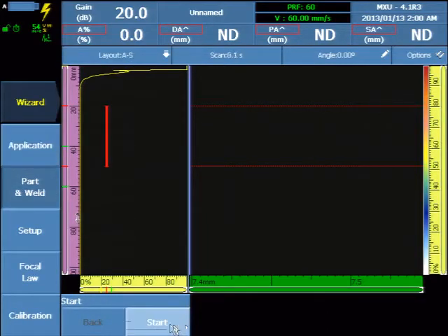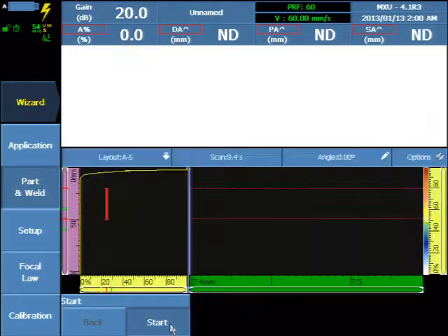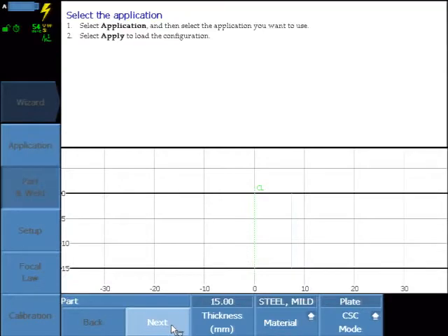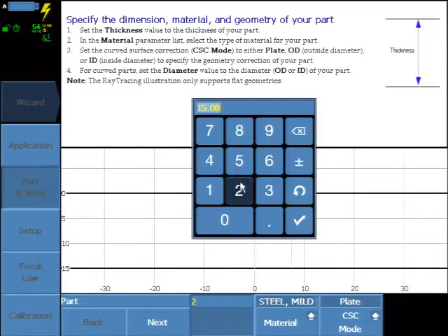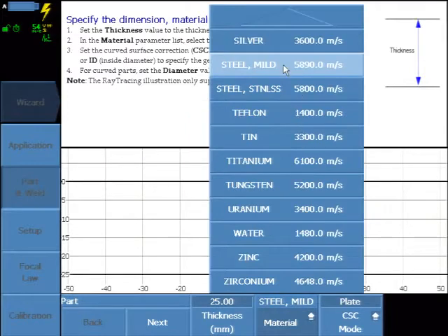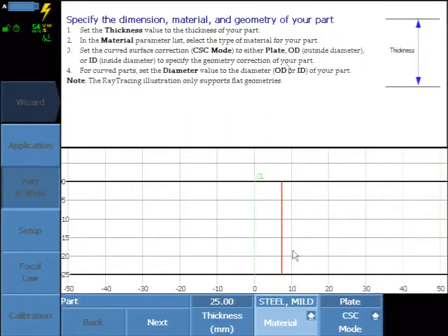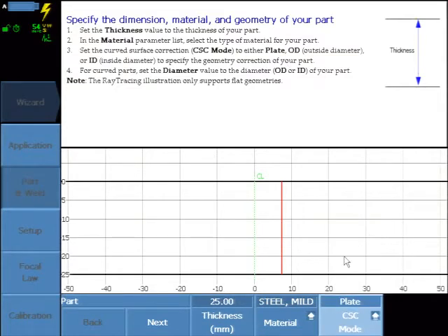Select Menu, Wizard, Part and Weld. Enter the component thickness. Select the component material, which will associate a default velocity, and select Plate for the CSC mode.